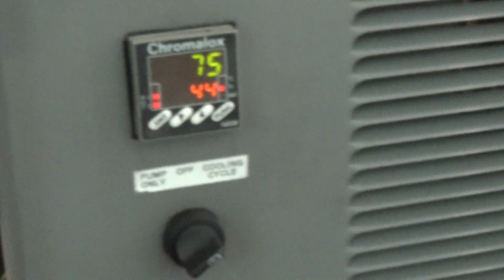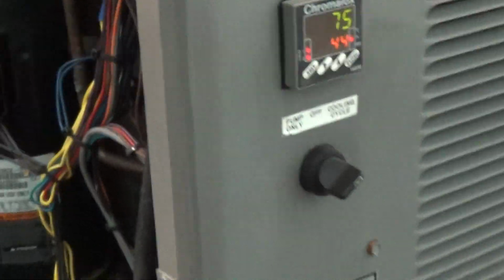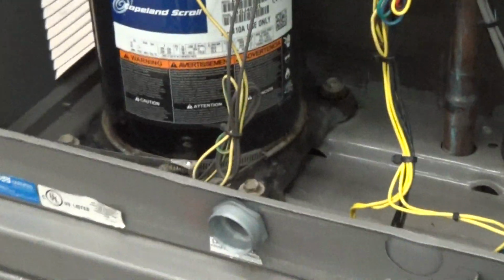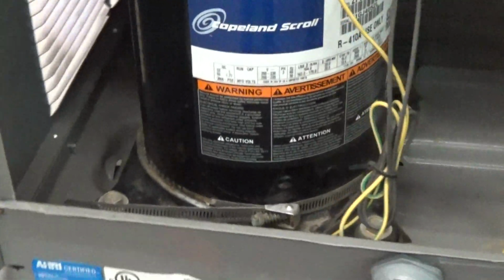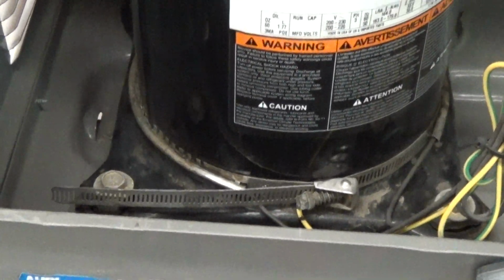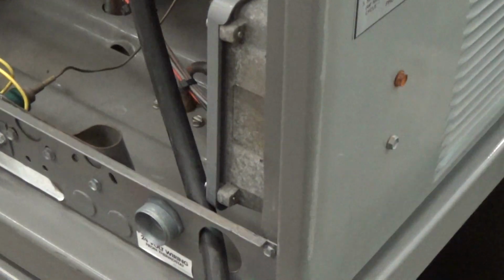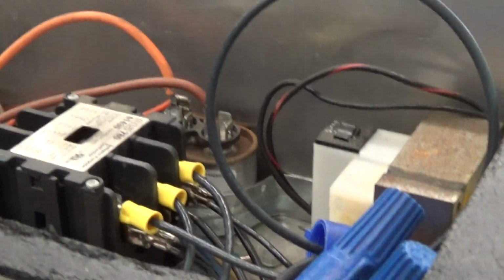So actually, while I was talking, it just kicked in. So right now the scroll compressor is running. This is an outdoor rated unit. It does have a heater band on the compressor, so you do want to keep that heater band on at all times, which basically means as long as you have live power going into the chiller. Up here in the control section, or the electrical section, that heater band will be on. So that's our scroll compressor.